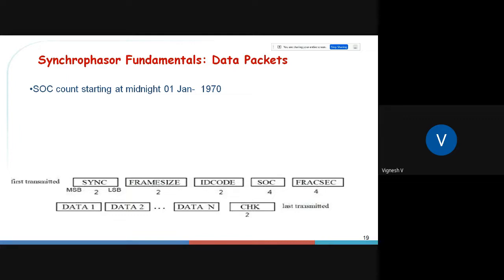The phasor data concentrator processes data packets from the PMU, which has its own structure, shown here with headers, data, and a check field. Sync, frame size, ID code, SOC, frac second are the headers; data 1, data 2, data n are the actual data; and the check is the tail of the data packet, ensuring things are correct from the PMU.